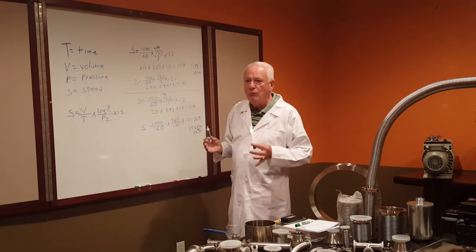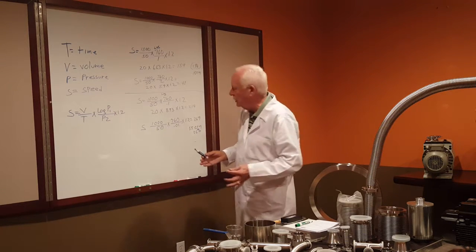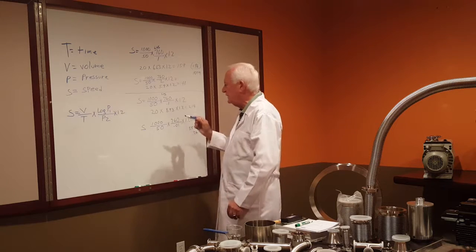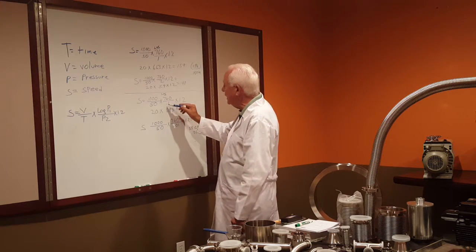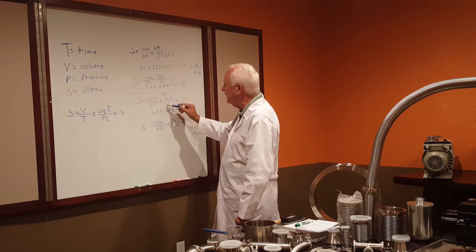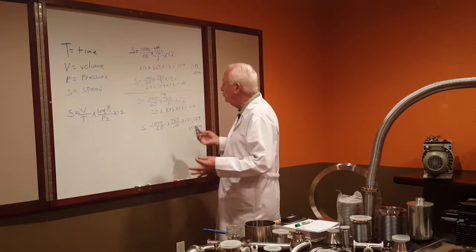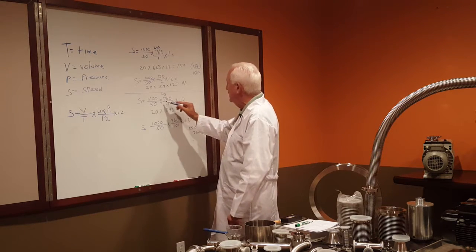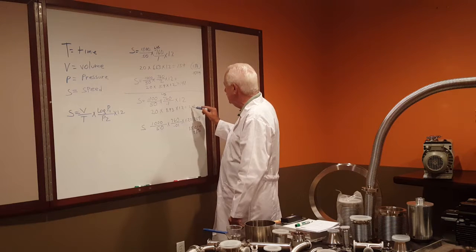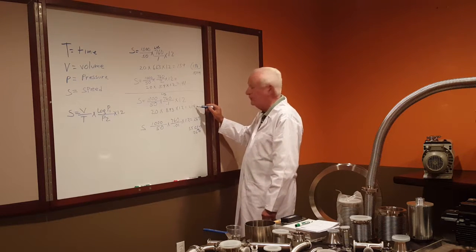This becomes even more dramatic the lower the pressure. Taking the same volume and the same time, but this time going to 0.1 torr — which is 100 microns — we're going to be able to do that with a 214 CFM pump.